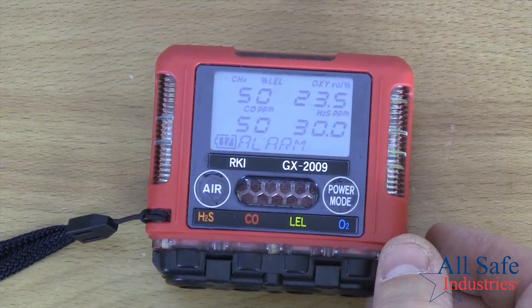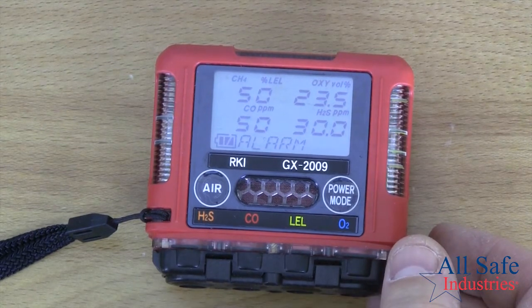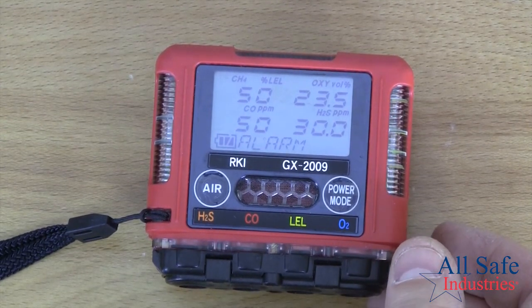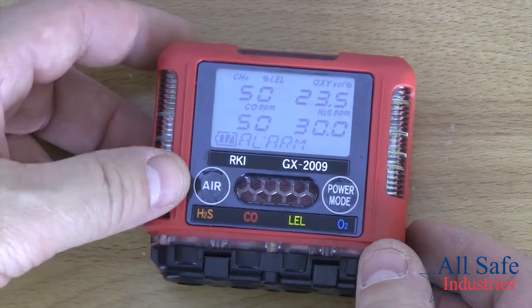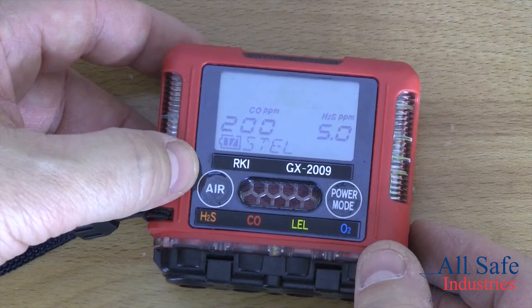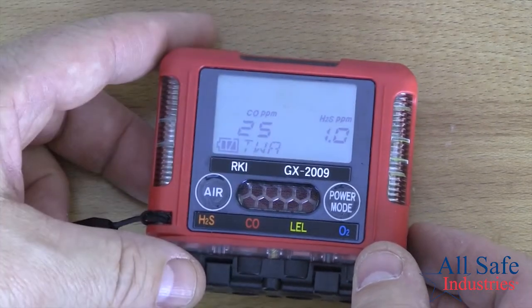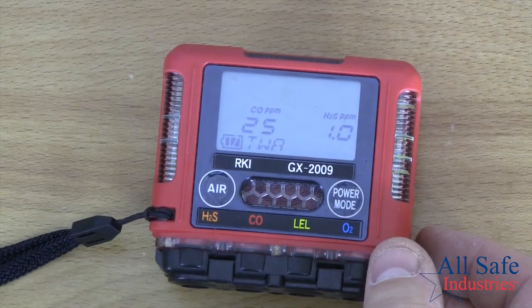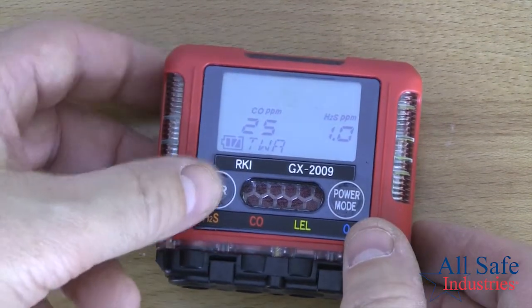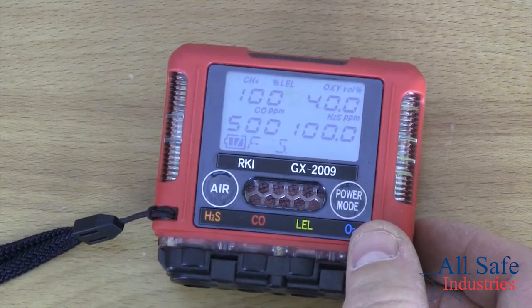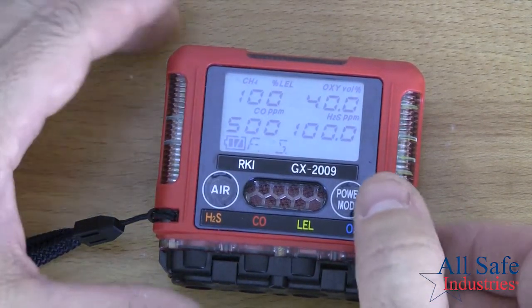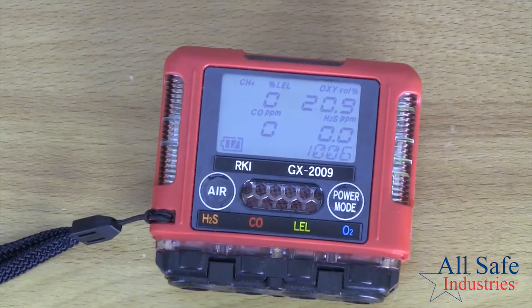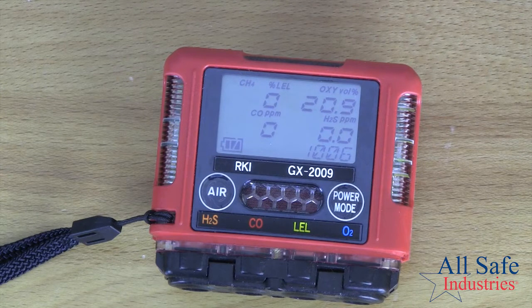So if gas concentrations continue to rise, you'll see the second alarm go off and it will beep and flash at you faster to create that urgency that you need to take action. And then one more press shows what the STEL alarm will go off at and what the time-weighted alarms will go off at. Again, only for the toxic gases on the STEL and the TWA alarms. And then one more press brings us back to the full-scale screen. So now we've seen all the alarm information. And one more press of the power mode button, and we're back to the regular gas reading screen. And you can see how all 4 gases are displayed simultaneously. So that's what the power mode button does for us if we just press it one press at a time.